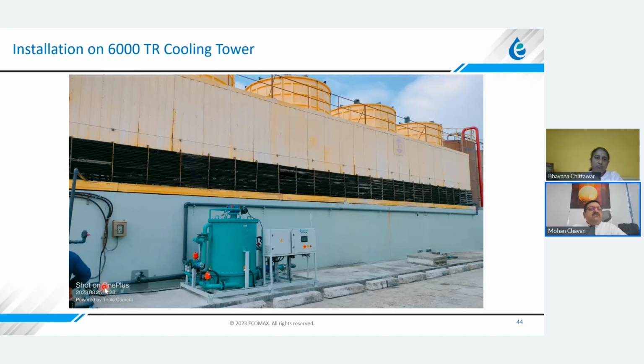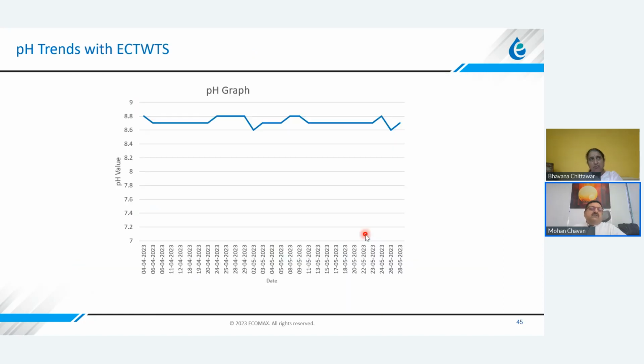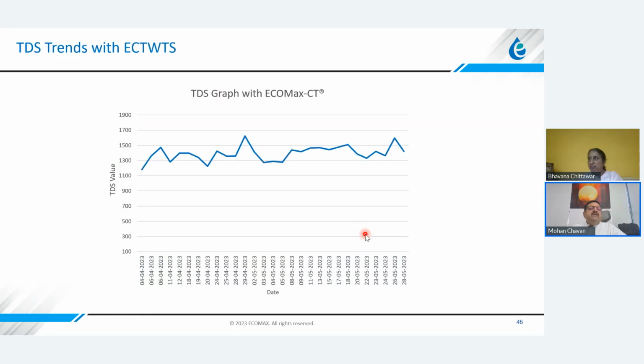This is another large installation for a 6,000 TR cooling tower. You can see here the cells are quite big. Okay, and this system is treating it. And when we say blowdown reduction, it's a measured blowdown reduction. We have here a flow meter which will measure the actual blowdown that's happening from the system. Here also, we could see that pH is maintained, TDS is also maintained at desired levels.